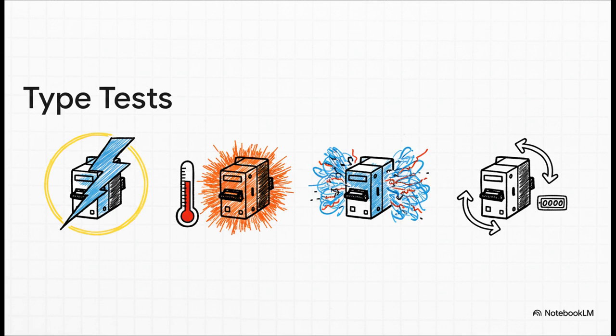Well, the answer is something called type tests, and they are absolutely grueling. They take a sample breaker into a special high-power lab and basically torture it. They hit it with artificial lightning, run it so hot for hours on end it's almost glowing, force it to break currents way bigger than it should ever see in the real world, and open and close it thousands and thousands of times to make sure nothing breaks.